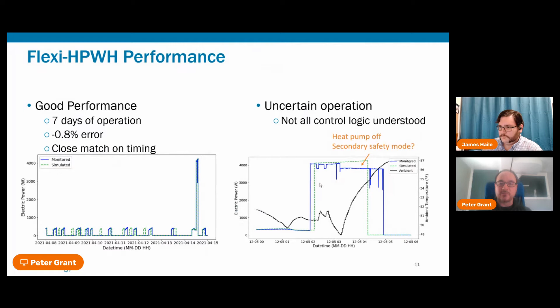Now, we used Flexi to do a parametric study looking at the annual impacts of several different control strategy and design changes when using the Creekside data sets. So we looked at different fixed set point and load shifting control strategies. And then we also looked at different system designs. The 4 system designs that we're highlighting here are what happens when you have that same 80-gallon heat pump water heater serving 4 apartments, versus that 80-gallon heat pump water heater with a 1-ton compressor serving 4 apartments. Or what if you have that 80-gallon heat pump water heater serving 3 apartments? Or what if each apartment has their own separate 50-gallon heat pump water heater?